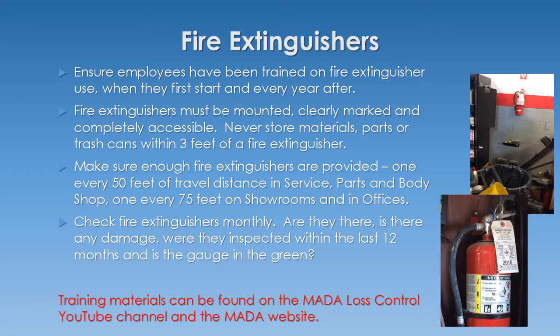Check fire extinguishers monthly. Are they there? Is there any damage? Were they inspected within the last 12 months? And is the pressure gauge in the green? Is there any indication that the fire extinguisher may not function as it needs to? Can you get to it? How is the housekeeping around it? Is there a clear path to the fire extinguishers? Make sure they're well marked so that they can be seen.